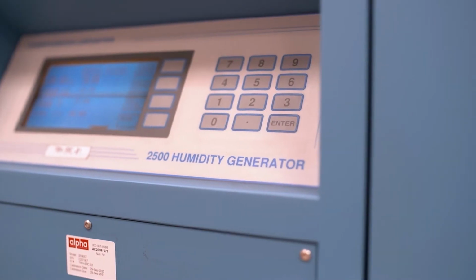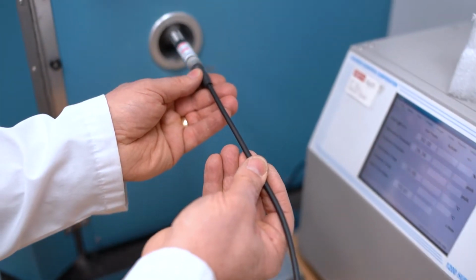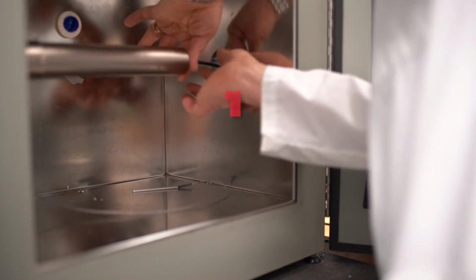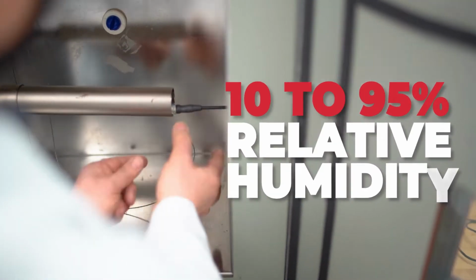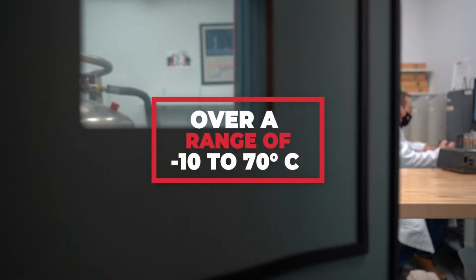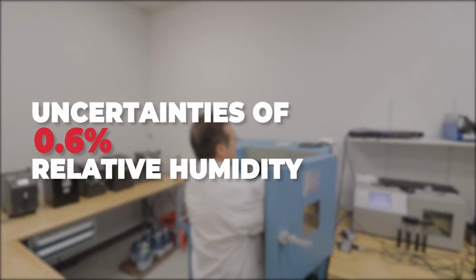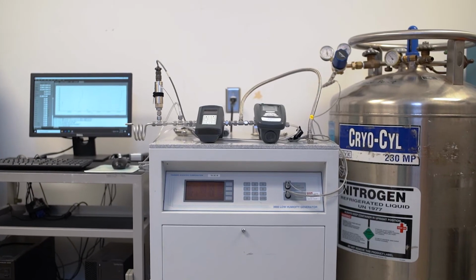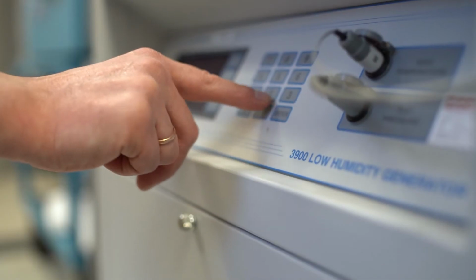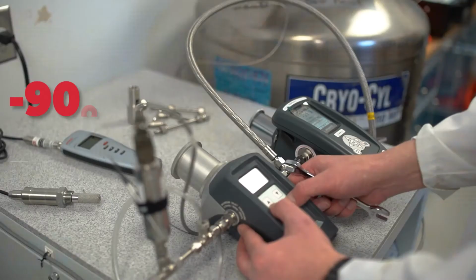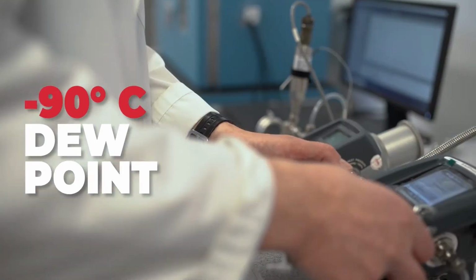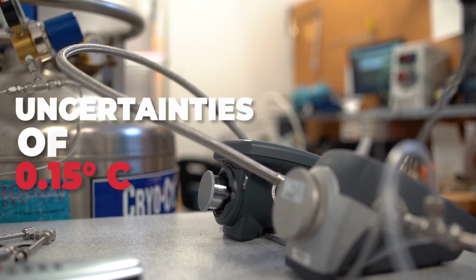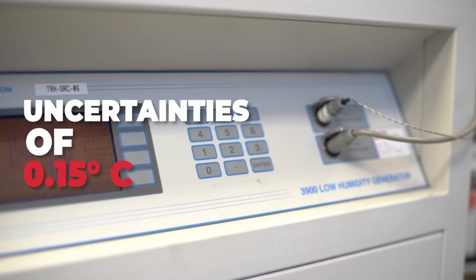By utilizing our Thunder Scientific 2500 chambers, we're able to achieve 10 to 95% relative humidity over a range of negative 10 to 70 degrees Celsius with uncertainties of 0.6% relative humidity. When low humidity values are required, our Thunder Scientific 3900 can get down to negative 90 degrees Celsius dew point with an uncertainty value of 0.15 degrees Celsius.